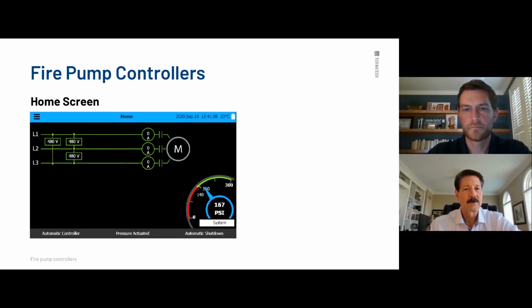You see your cut in, cut out on the bottom right. You see your system pressure, 167. Across the bottom tells you what type of controller you have. And top right, as he mentioned, the temperature. So for the most part, most of the customers that you're dealing with probably aren't very tech savvy. And this makes their lives really simple. It's very easy to go in and realize red is stop, green is go or energized, and yellow is caution. And just pointing a few things out, 5 minutes and anyone can understand what the screen means. And that's what the technology has done.